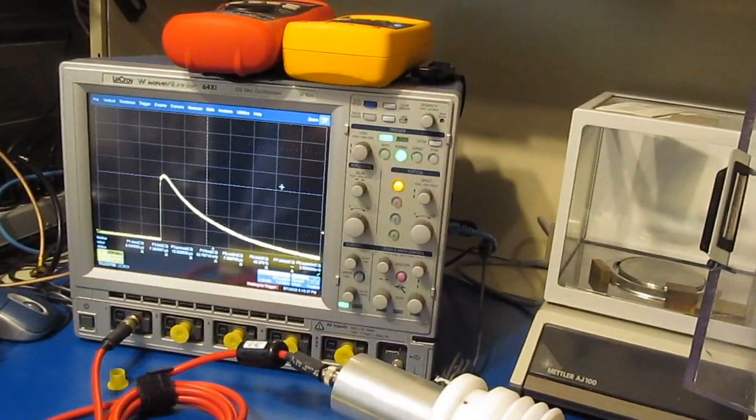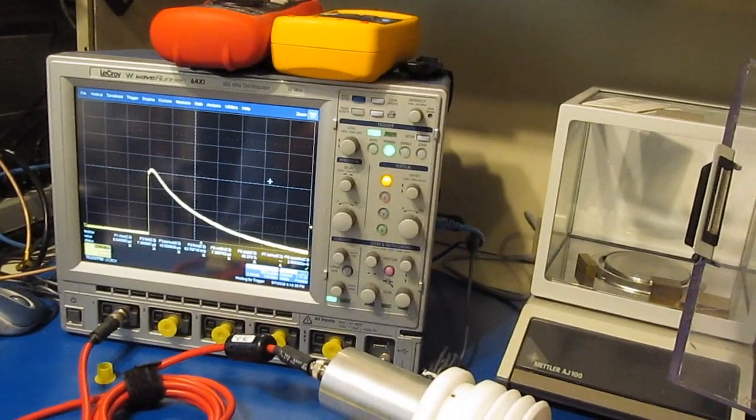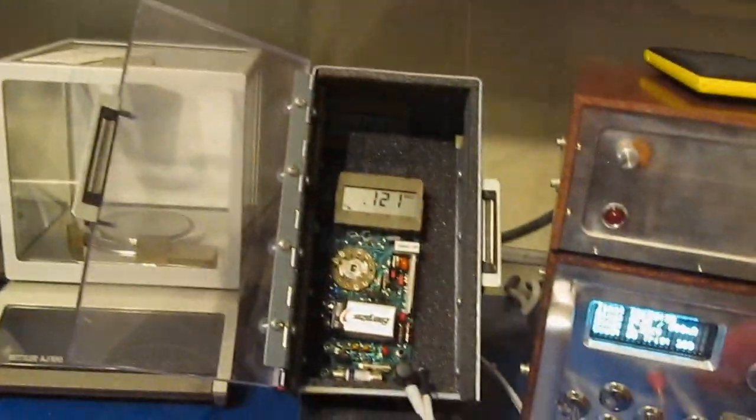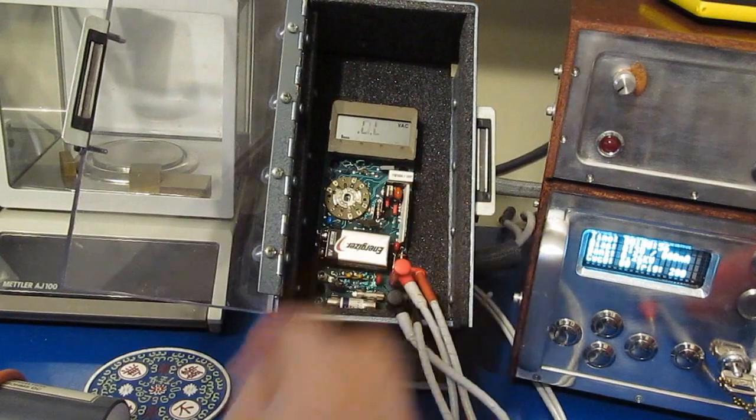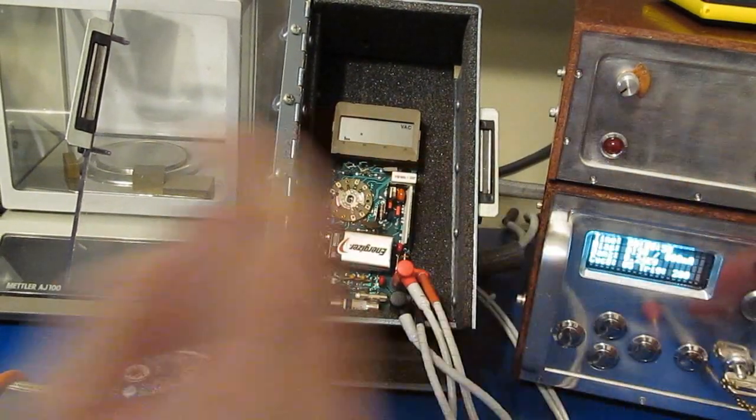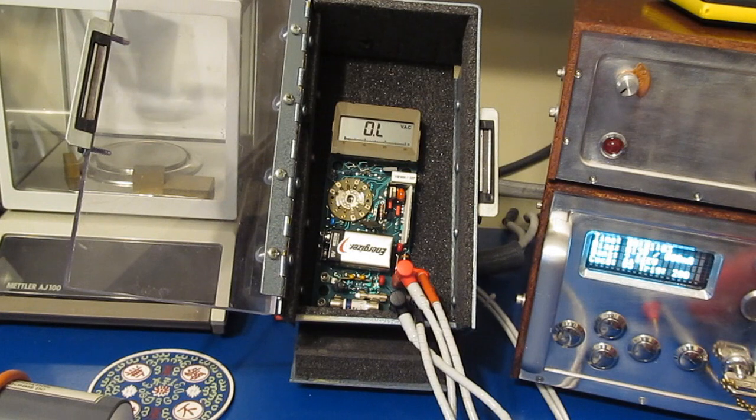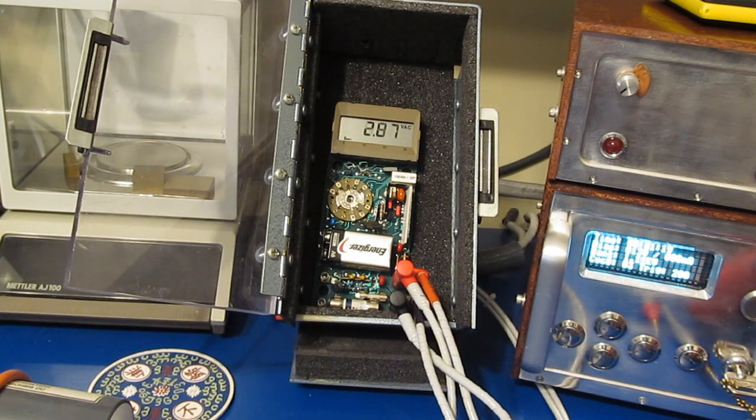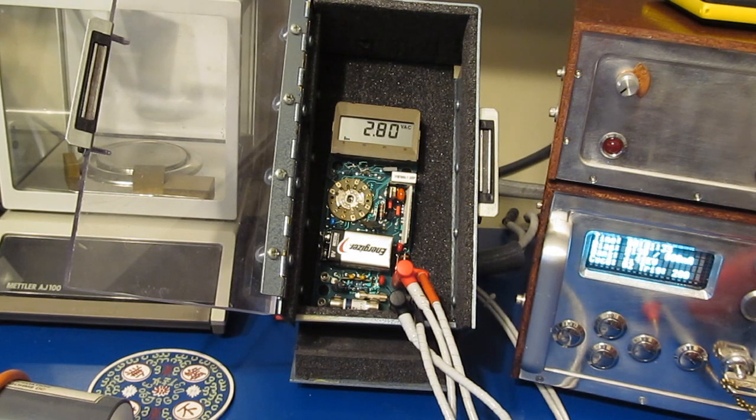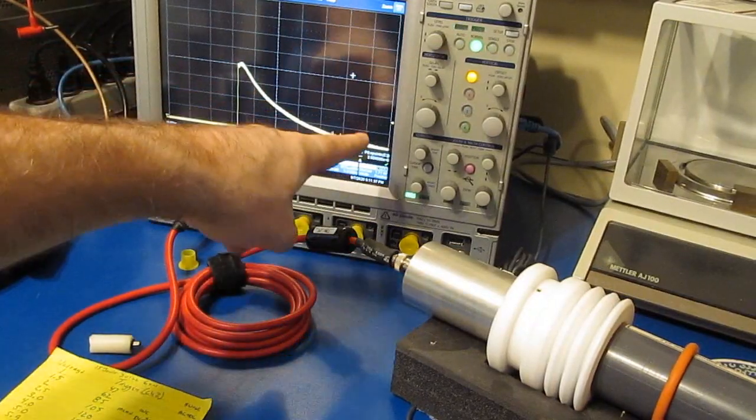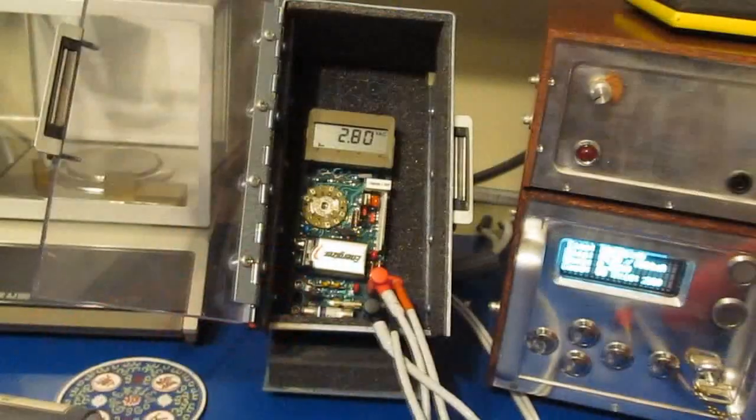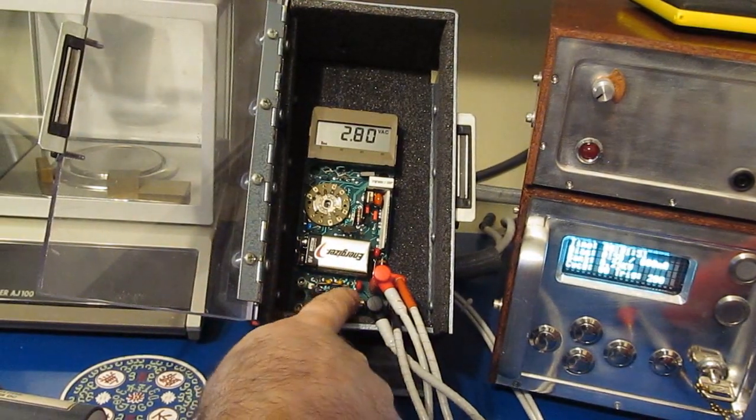Looks like it's still fine. All right, you can see we are now four divisions up or 4,000 volts peak. Again, we'll be applying five transients positive - let's just see what happens now. You can see it really doesn't change the shape of the profile at all.